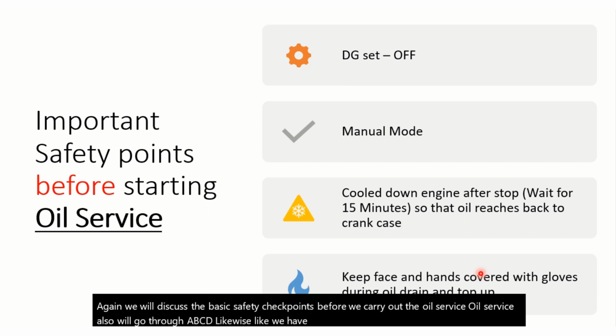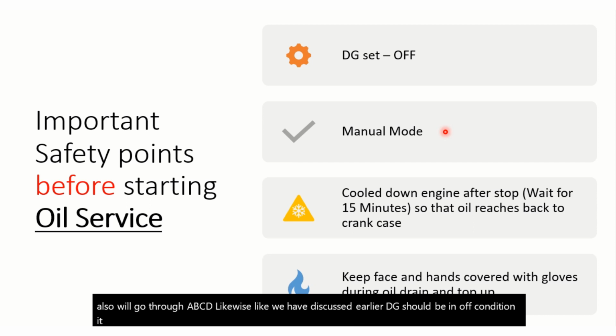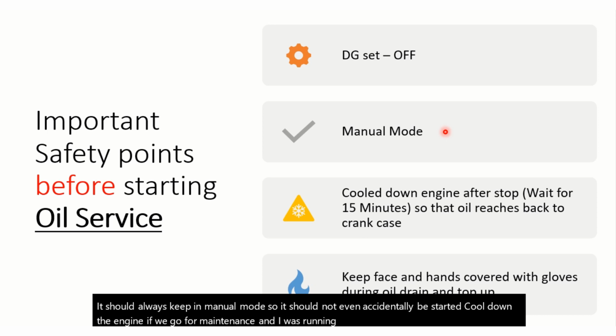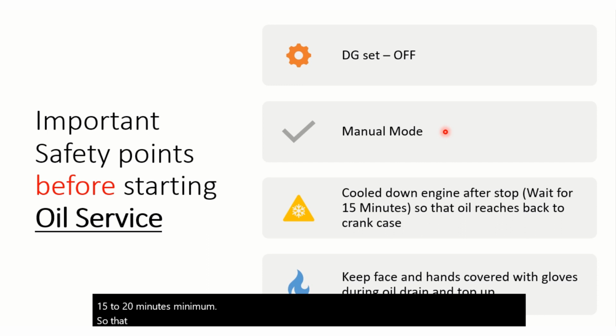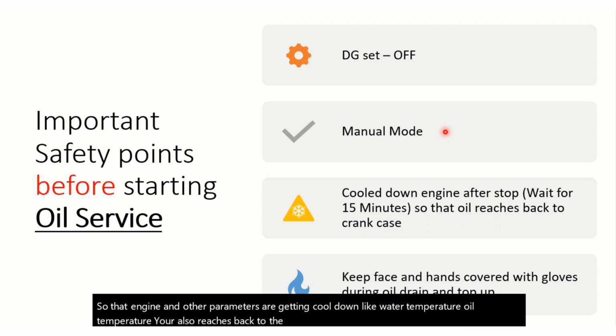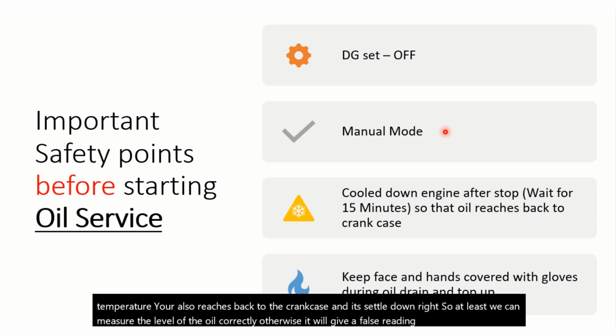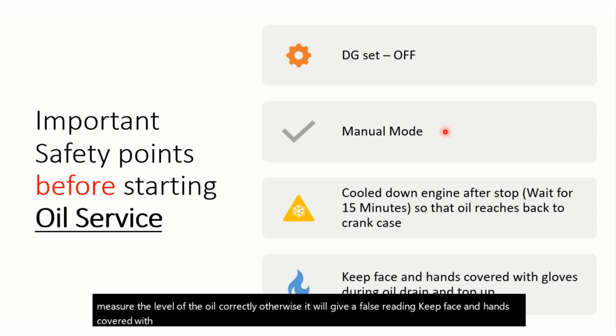The DG should be in an off condition. It should always be kept in manual mode, so that it cannot even accidentally be started. If the DG was running, cool down the engine before maintenance: switch off and wait a minimum of 15 to 20 minutes so that the engine and other parameters, like water temperature, cool down, and the oil returns to the crankcase and settles. Then we can measure the oil level correctly, otherwise it will give a false reading. Keep face and hands covered with gloves during the oil drain and top up.